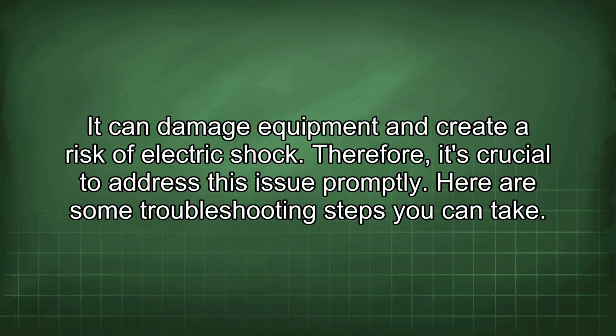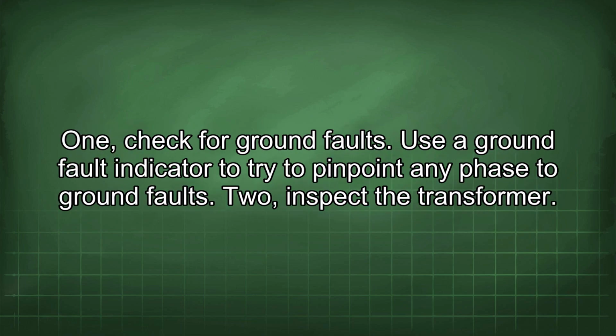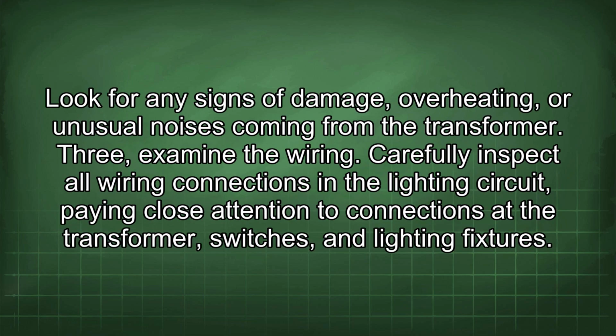Here are some troubleshooting steps you can take. 1. Check for ground faults. Use a ground fault indicator to try to pinpoint any phase to ground faults. 2. Inspect the transformer. Look for any signs of damage, overheating, or unusual noises coming from the transformer. 3. Examine the wiring. Carefully inspect all wiring connections in the lighting circuit, paying close attention to connections at the transformer, switches, and lighting fixtures.